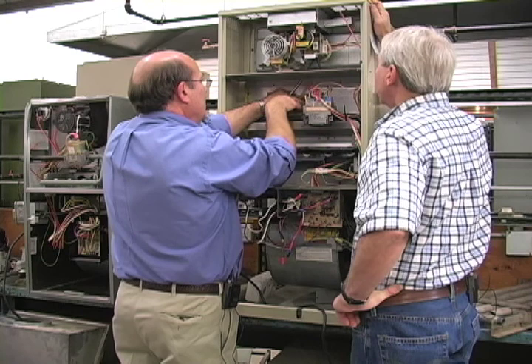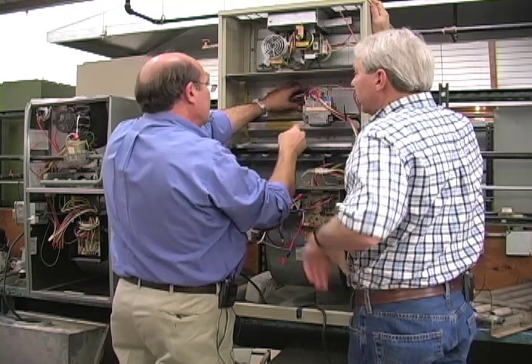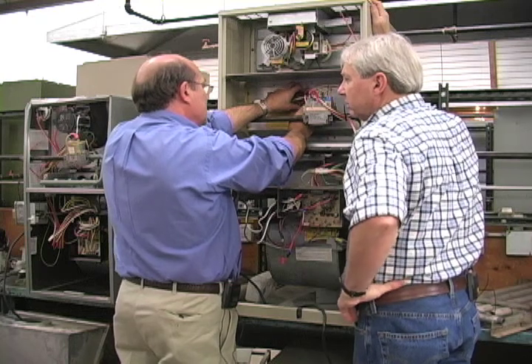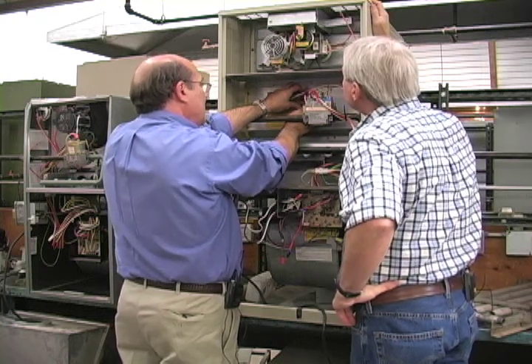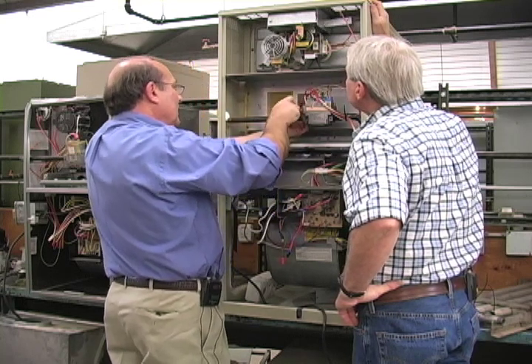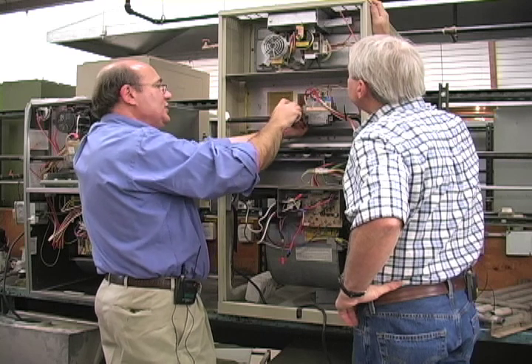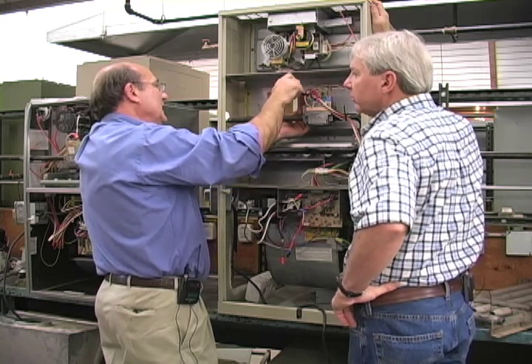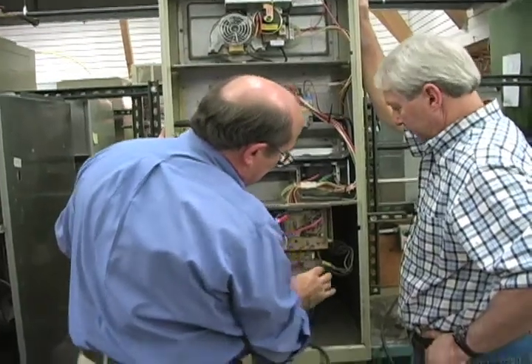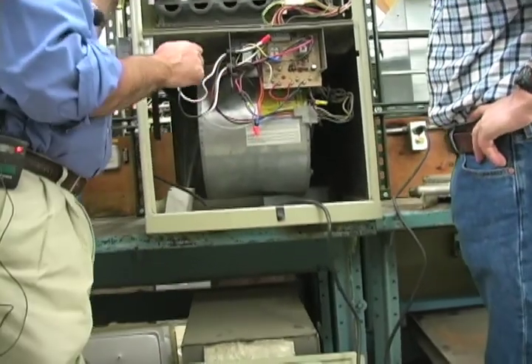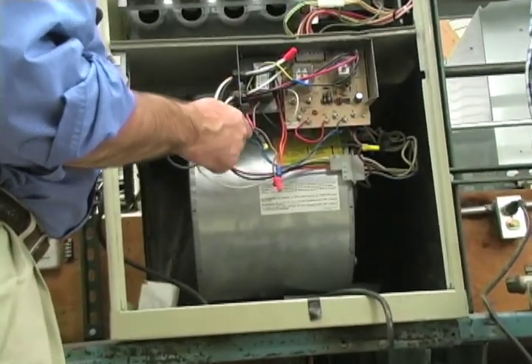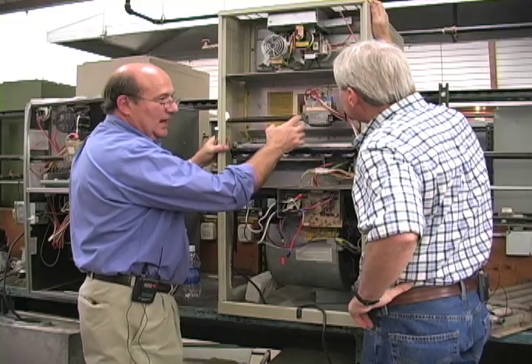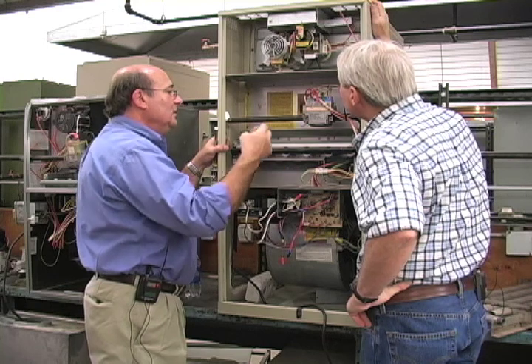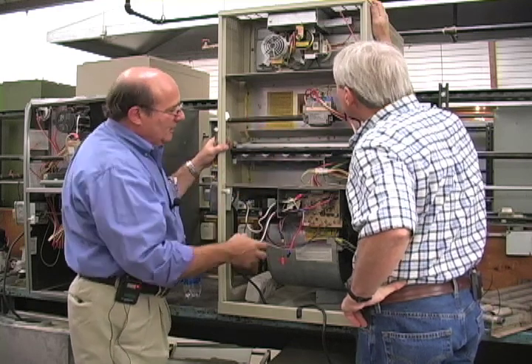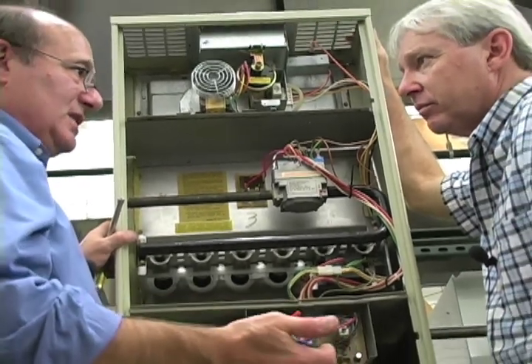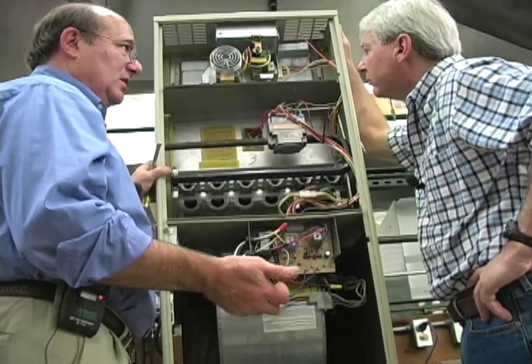Now, oh, go ahead. Okay, where's the high and low limit? Because that's a safety and that's a safety. Well, these are both limit switches. So they're high limit switches, and they shut down the gas valve. The question, of course, is what turns on the blower? We don't have that combination fan limit switch anymore. Well, the blower is activated through the solid state controller down here. A lot of these have dip switches on them where you can set the blower delay, the delay on and the delay off. And so once this system is up online, we got the pilot, we got the gas valve open, we got gas flowing, we got combustion, then we go into a time cycle. Right. And we turn the blower on based upon a predetermined time interval. Could be 30 seconds, could be 180 seconds.